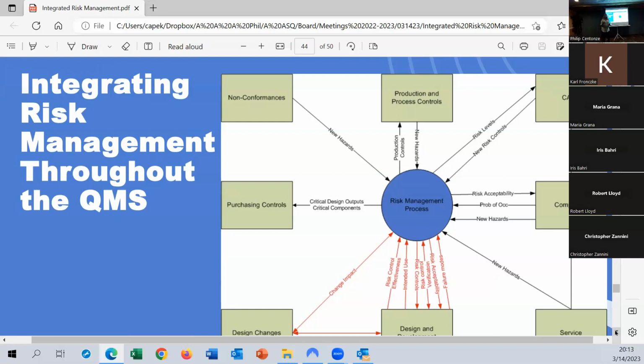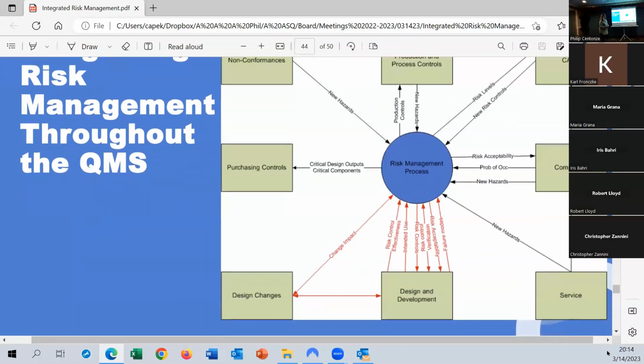CAPA, usually you assign a risk level for the CAPA. We need to look at our risk analysis and determine the issue that can be caused and how severe that CAPA is. Complaints, that's an area that the FDA really looks at, right? And you need to go back to your risk file and show that you've addressed all of the root causes of those complaints. And then even in service, we might identify new hazards that we can go update our risk file. So pretty much everything that we do revolves around risk. Any information we gain, we need to feed back into a risk file to make sure that they're updated and that our overall residual risk is still at an acceptable level.